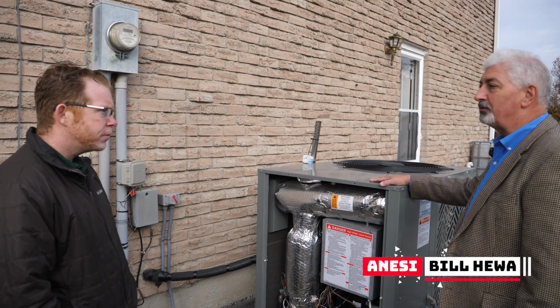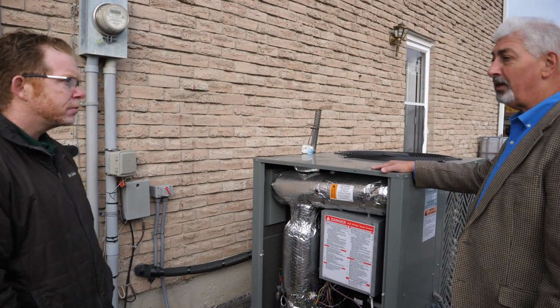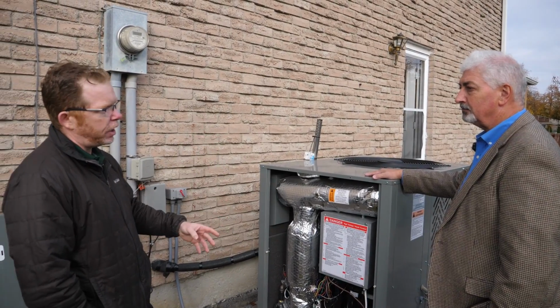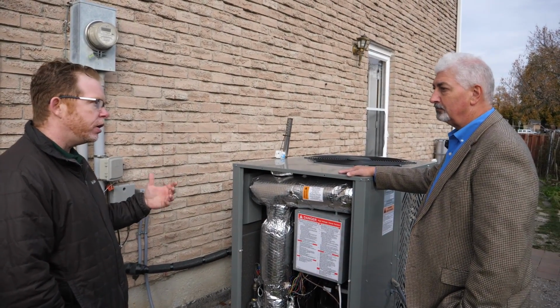We are well below 60 dBA, which is the threshold that you have for a lot of the electric heat pump products. So as far as installation goes, really you're going to install it just like you would any kind of heat pump. Don't put it next to their deck. Don't put it next to their bedroom door. The noise we're hearing right now, what is that noise that we're hearing as the unit is running?